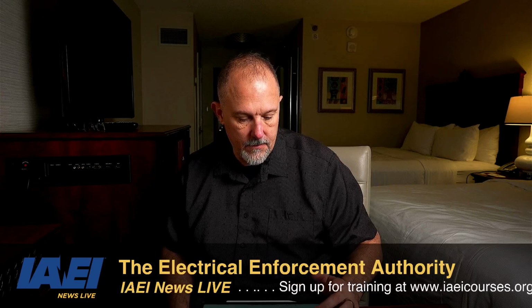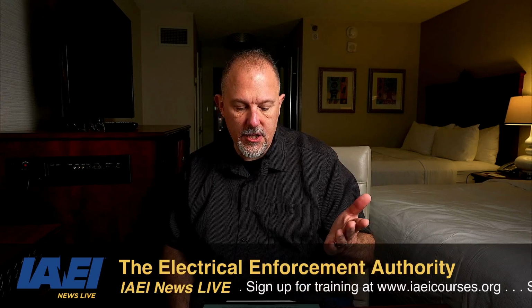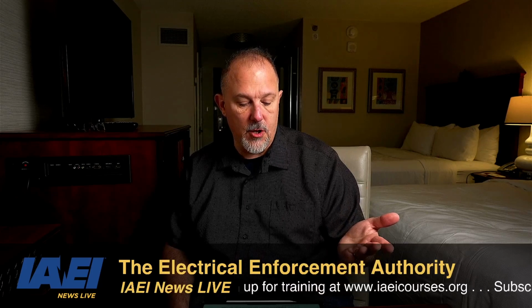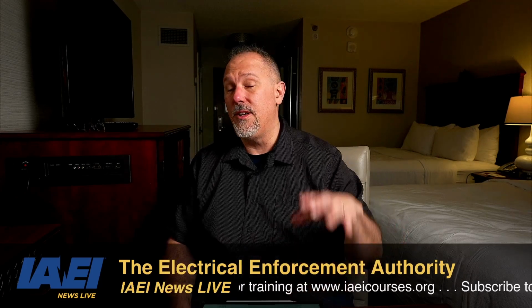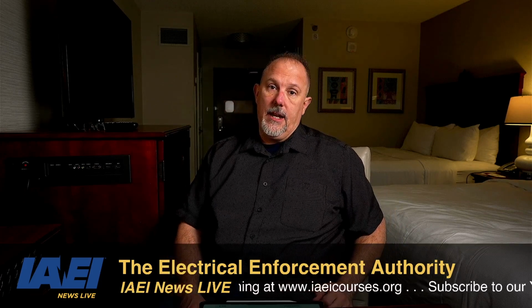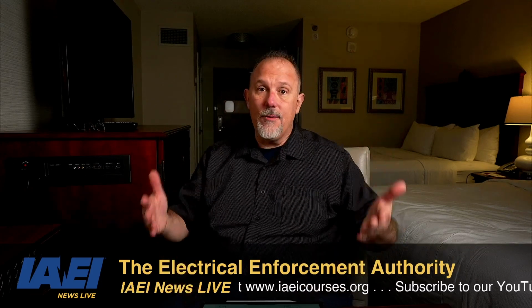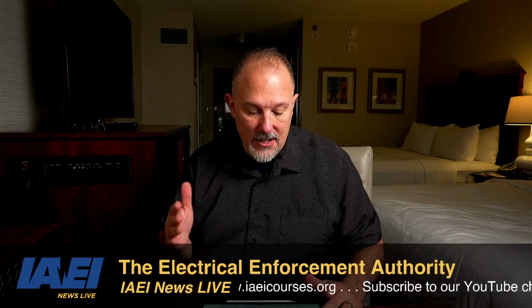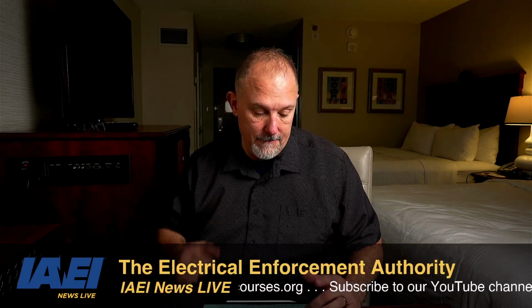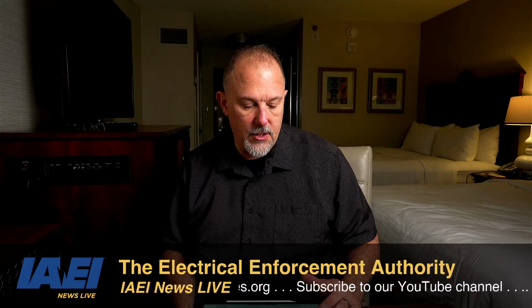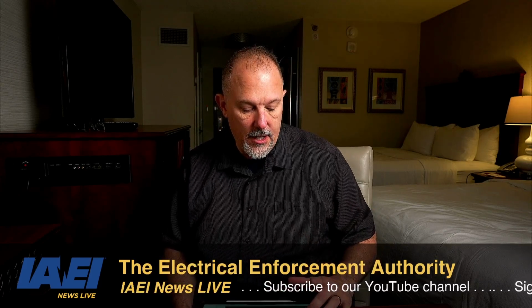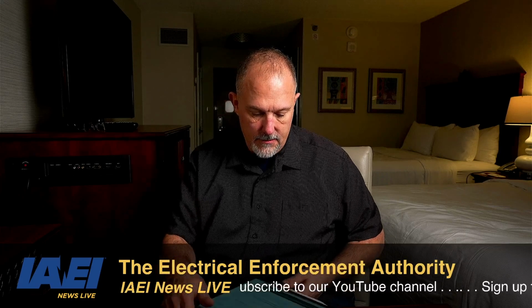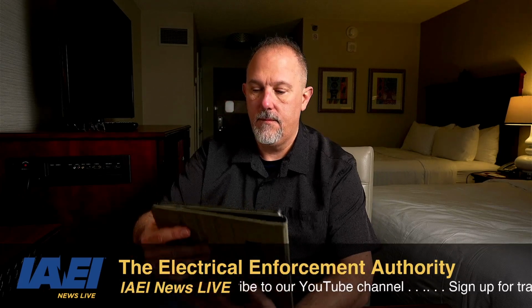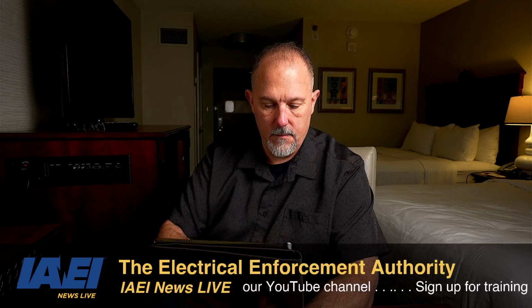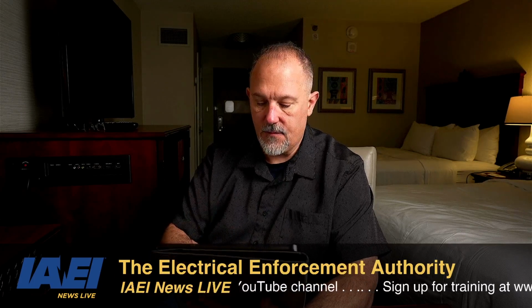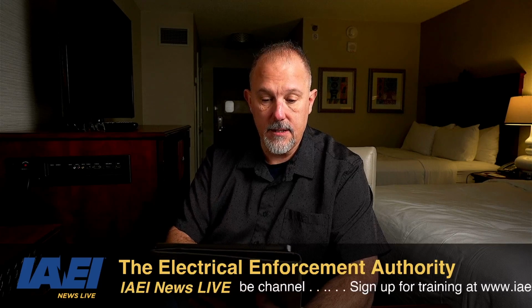All right. Ground fault circuit interrupter protection for receptacles on 15 kW or smaller portable generators. I know this was highly debated, and well, you know where it ended up. There were a lot of people that did not want to see this go in, but it went in for portable and smaller generators. So that receptacle needs to have GFCI protection. And I think, is that the last one? Is that the last? GFCI, yeah, that's 44. Oh, no, that's it.